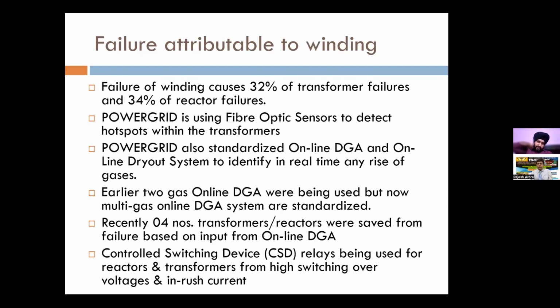Then failure attributed to windings. We have standardized FO sensor to detect the hotspots inside the transformer. Then online dryout system, online DGA were also used. So these have also been helpful in cases where there is any incipient fault inside the winding. Then control switching device have been used in reactors and transformers, which prevents any high switching overvoltages and inrush currents. So all these methods have helped us in reducing the failures which are attributable to winding. So with this, I conclude my presentation.